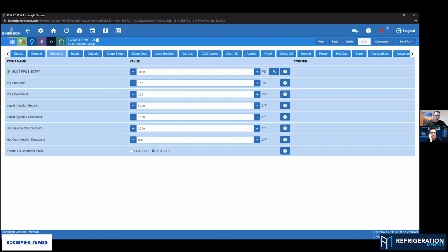Yeah, so for liquid injection, the value we use is the calculated superheat on the suction line for the medium temperature coming back, from our pressure transducer and suction temperature. As long as we have those two inputs, we can get a medium temp suction superheat. We give that a set point of 50 degrees of superheat in this instance, and then also a dead band. So when would we like to cut in and cut out, in old school terms, right?